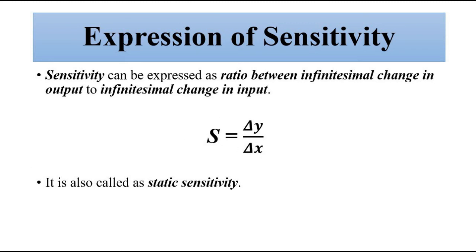This parameter is very important because it defines how much change in output will be brought about by a certain change in input. Sensitivity is always specified in the specification sheet for a particular measurement device, whether it is a temperature sensor, pressure sensor, or any other sensor. In cases where the device behaves differently across ranges, the specification sheet will indicate the sensitivity for each range — beyond a certain point the sensitivity will be different.